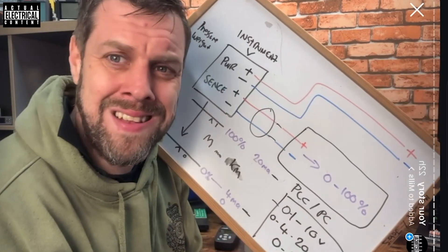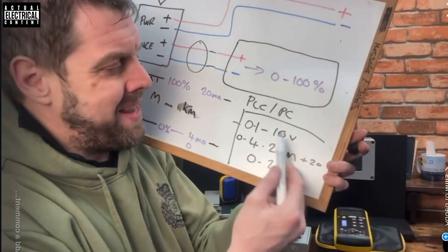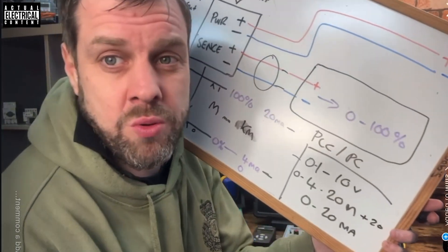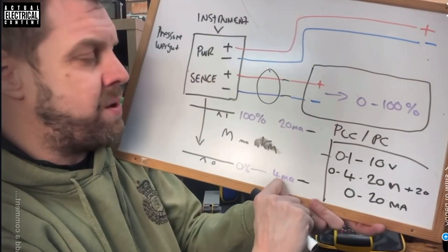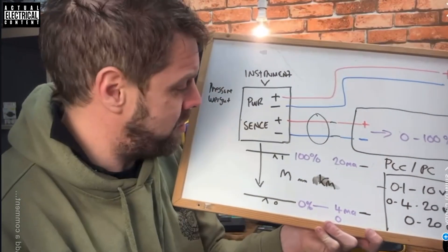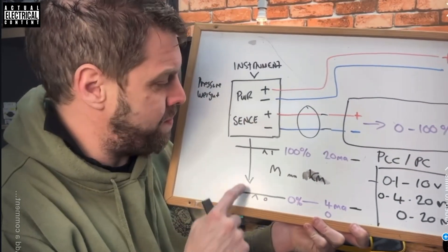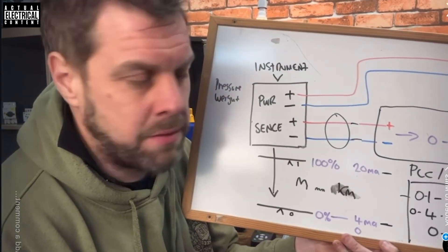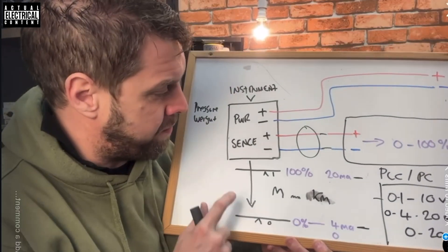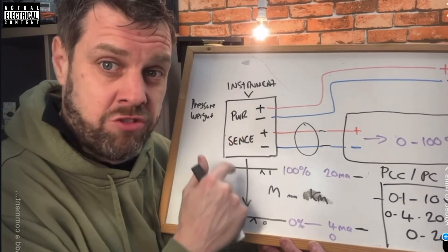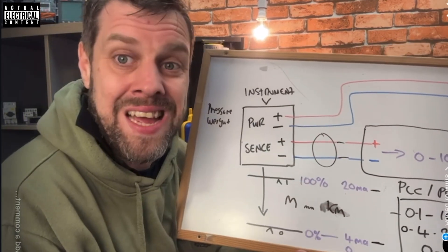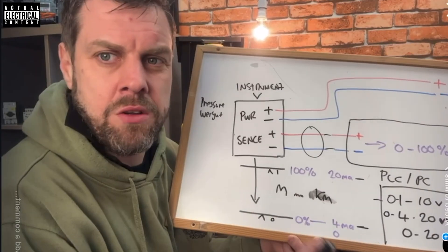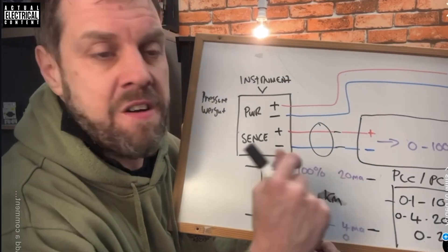If you think about it and write on a bit of paper as a line - naught to 10, say it was a speed - forward one would be slowly forward, 10 would be fast forward. What about if you negative it? If you went negative 10 volts it'd be fast backwards. But at zero you've got nowhere to go. With four to 20 milliamps, you get a little span in the middle which is a definite zero point. So from plus four to negative four you get a dead space so you know whether you're going one way or the other.